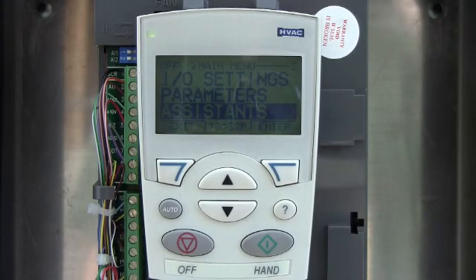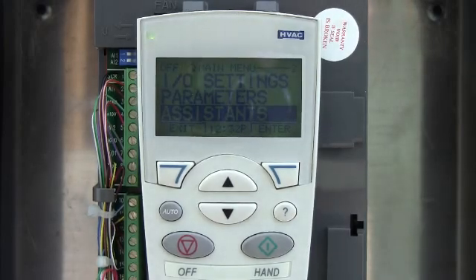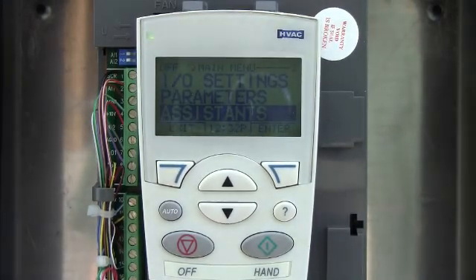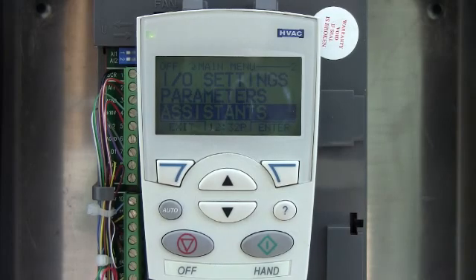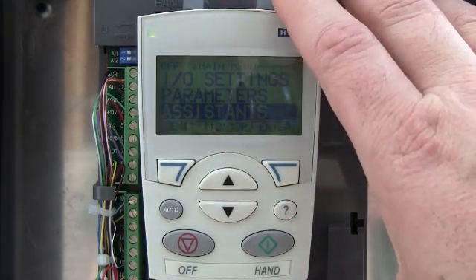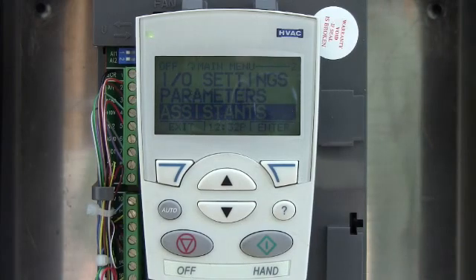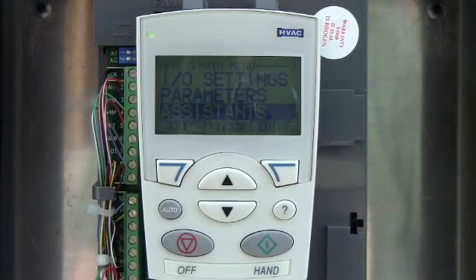Assistants — this one right here, I would strongly recommend not going into. The reason is it will drive you nuts. It's cumbersome, it takes forever, and by the time you get done with it the drive isn't going to work. Usually it locks it up so tight that I even have problems getting in there and getting it back to factory default so that I can program it again. So I would really recommend staying away from that. It doesn't offer much. It was designed to be similar to a wizard on your computer, but the problem is it doesn't work, in my opinion. Anyway, that's the main groups — just wanted to go over that with you.